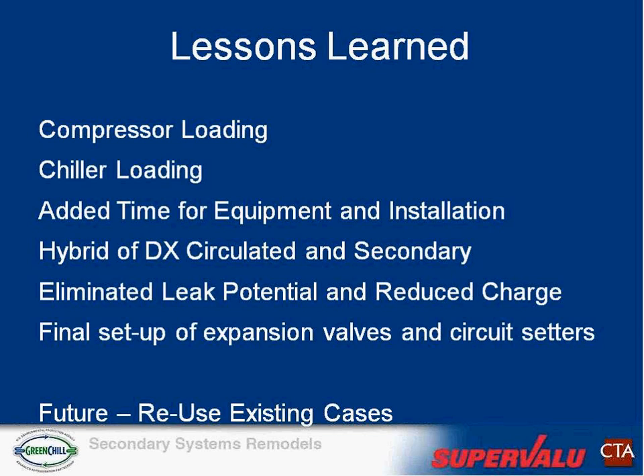And then we learned that we eliminated some leak potential, just by reducing the amount of copper refrigerant piping in the facility, and we definitely reduced our refrigerant charge. I would say you could probably just count on 50% as a good average. And I covered this already: final setup of expansion valves and circuit setters is something that needs to be done after everything's up and running.